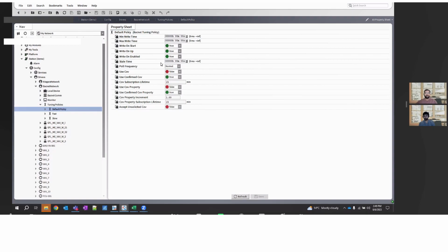Then we have the poll frequency, which we were discussing prior to this, where there are three options available: fast, normal, and slow. As a thumb rule for fast, I keep points like pressure, Boolean inputs, and alarms. These are high value points which need to be updated in my system as and when they are generated. Alarms are critical. If the fan has started, I need the status instantly on my system. For slow, I go for points which do not update quite often, like alarm set points, occupied cooling set points, airflow set points, and so on.